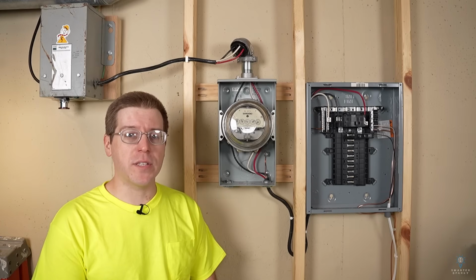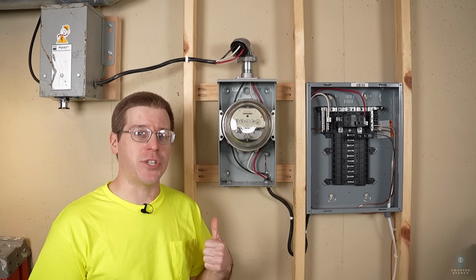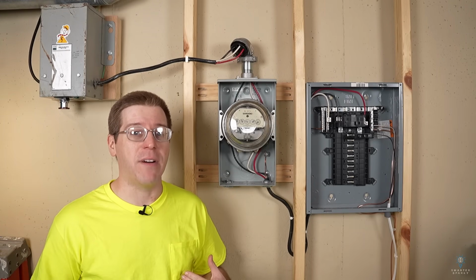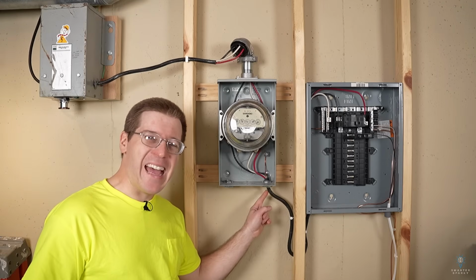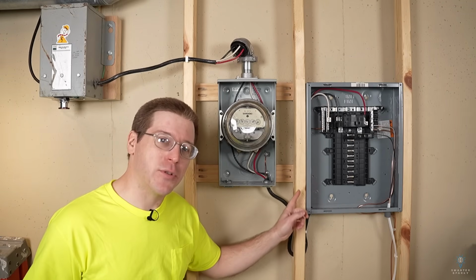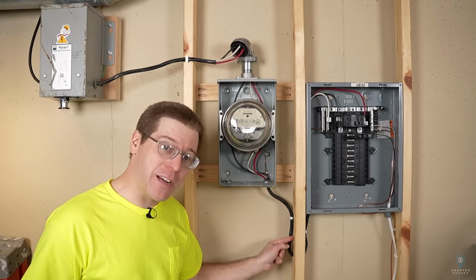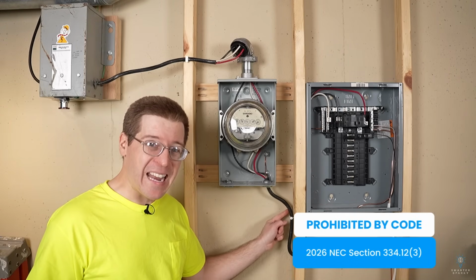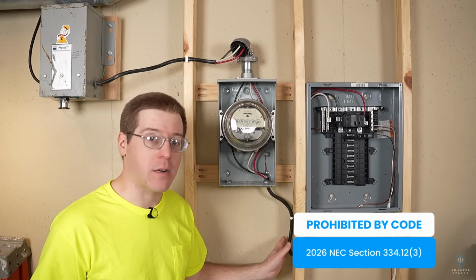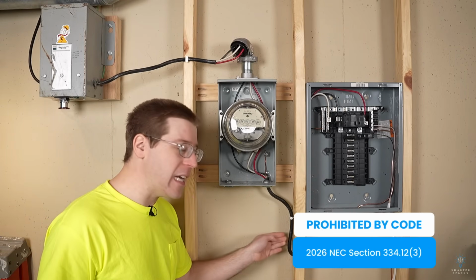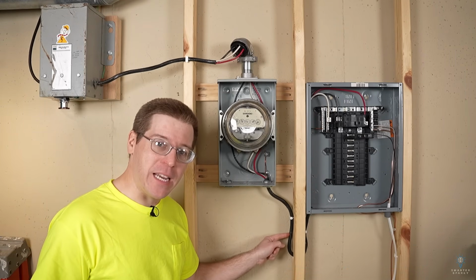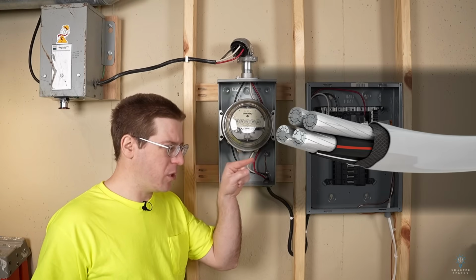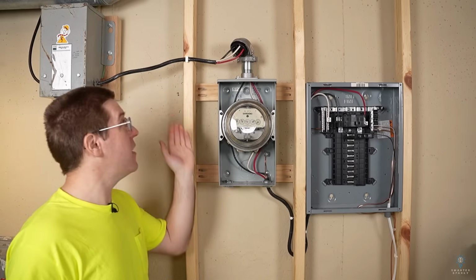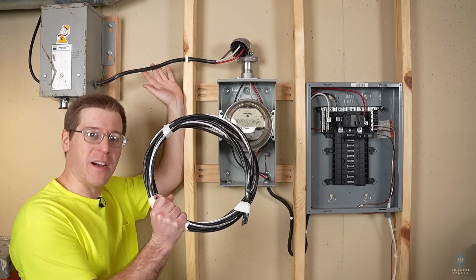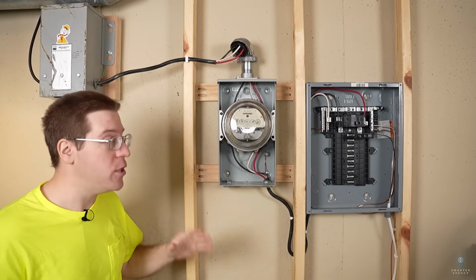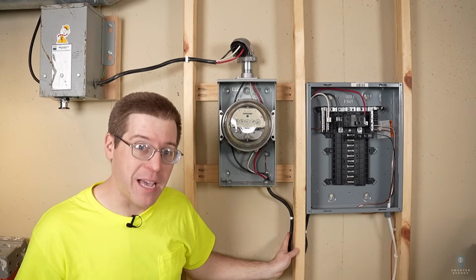The second thing I want to address real quick is, because this is a demonstration, I'm having to use the materials I have on hand. So because of that, I'm using NM cable as my service entrance conductor stand-in. It is actually illegal to use Romex or NM cable as your service entrance conductors. It's not rated for it. So we're gonna need to pretend that this stuff right here is SER wire, which would look something like this right here. Additionally, this overhead wire would actually be this stuff right here, triplex wire. We're gonna have to use these stand-ins and we're gonna have to use our imagination a little bit.